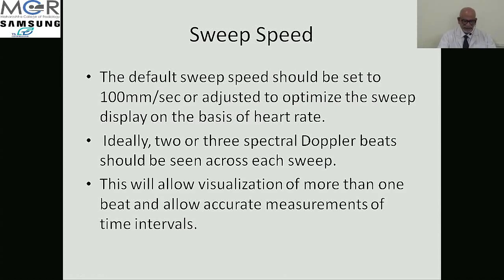Now sweep speed, that is how many envelopes can be shown on a screen. The default sweep speed should be set to 100 millimeters per second, or adjusted to optimize the sweep speed on the basis of heart rate. Ideally 2 to 3 spectral Doppler beats should be seen across each sweep. If you have fewer envelopes, you can measure them properly. If you have more envelopes, you will find it difficult to measure them.